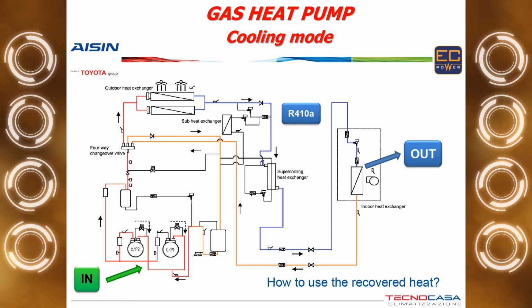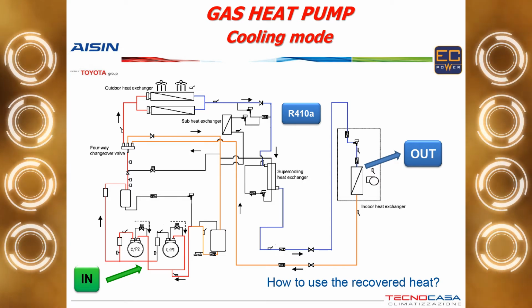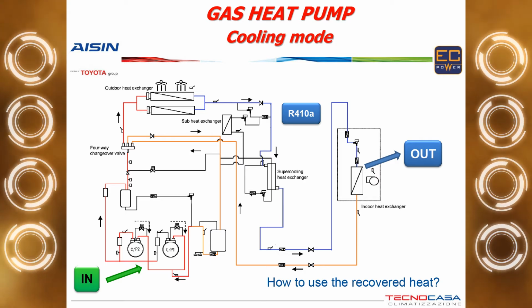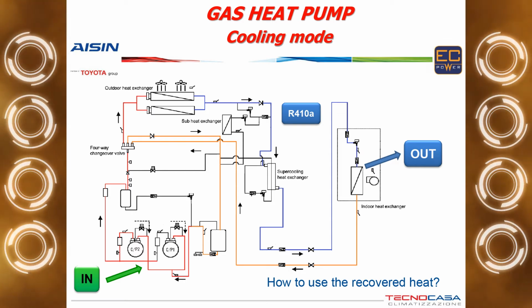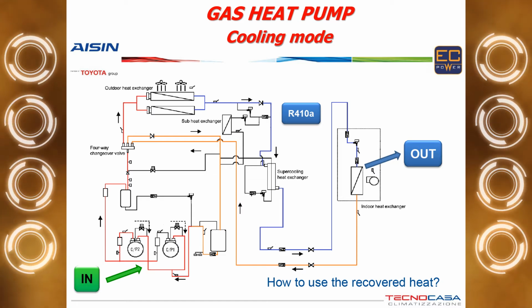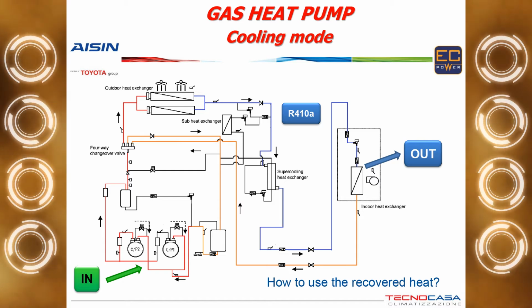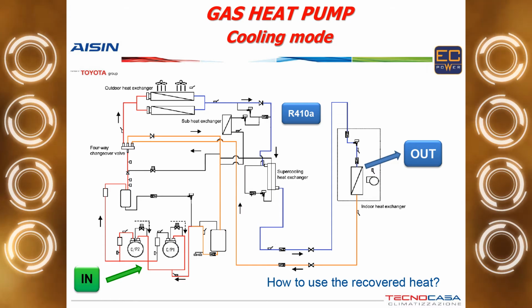Then, of course, we have indoor units, which can be direct expansion indoor units, so where the freon goes directly for the evaporation. And here we have an electronic expansion valve, which is driven inside the indoor unit by the superheating of the mixture in the evaporator, and then we go back to the outdoor unit and back to the accumulator. So we take the energy from the engine, the mechanical energy, and we use the mechanical energy to drive the heat pump cycle by dragging energy from the indoor unit to the outside in this case.